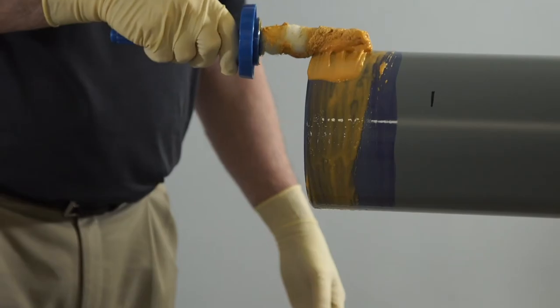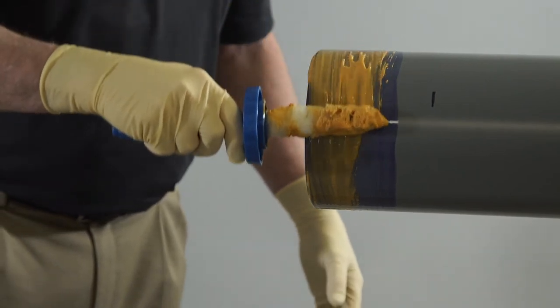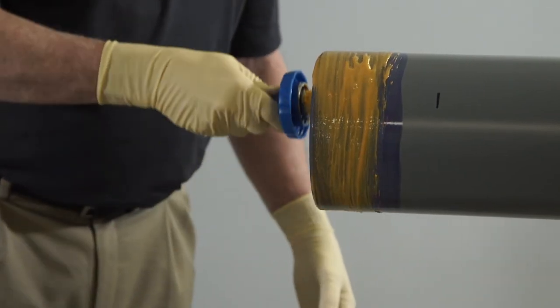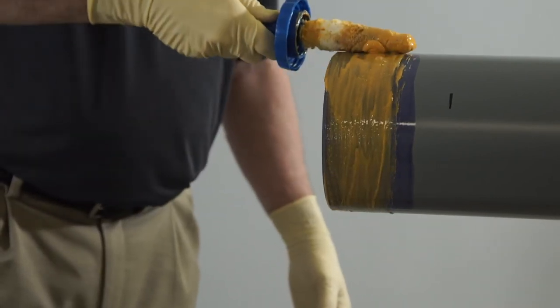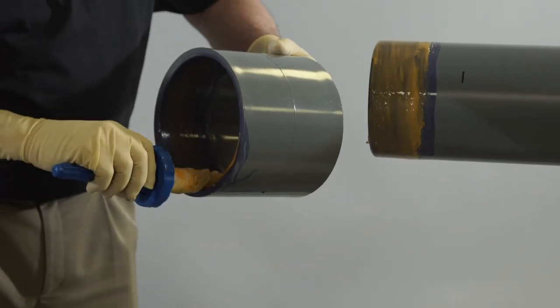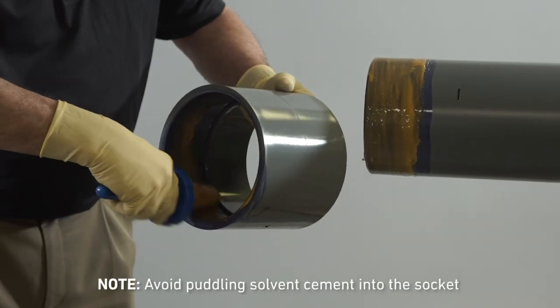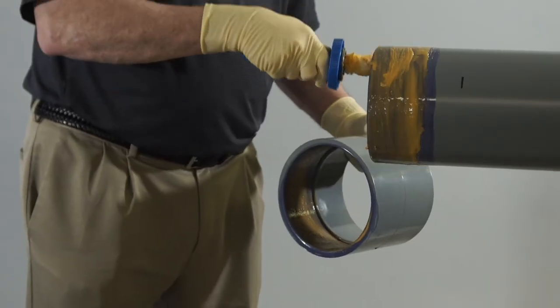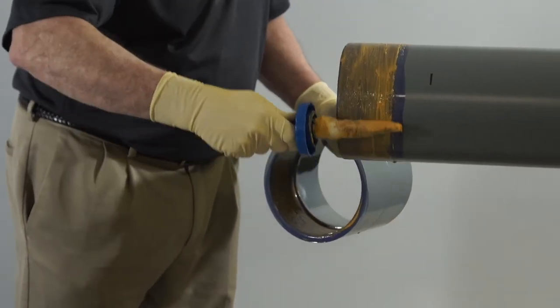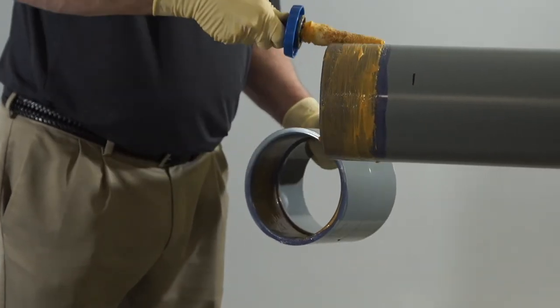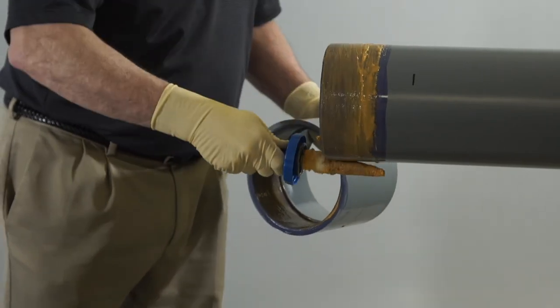Aggressively apply a full, even layer of solvent cement to the pipe, equal to the depth of the fitting socket. Do not brush the layer out to a thin paint type layer, as this will dry too quickly. Then, aggressively apply a medium layer of solvent cement into the fitting socket. Apply a second, full, even layer of the solvent cement on the pipe. Most joint failures are caused by insufficient application of solvent cement.